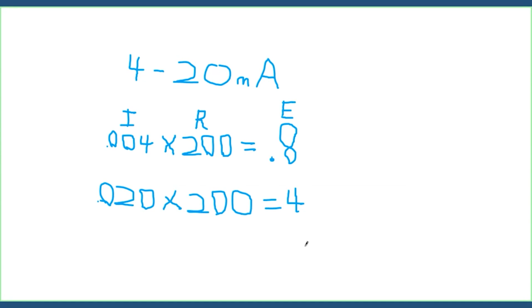You may be thinking right now, what good does this do me? Well, if you use any 4 to 20 milliamp pressure transducers with the DE3000 or even the new DE4000, you know that we wire those things up differently and we flip the dip switches differently. Inside those terminal boards, which is one of the reasons why we flip the dip switches, we short out our signal side coming in from the pressure transducer to ground through a 200 ohm resistor.